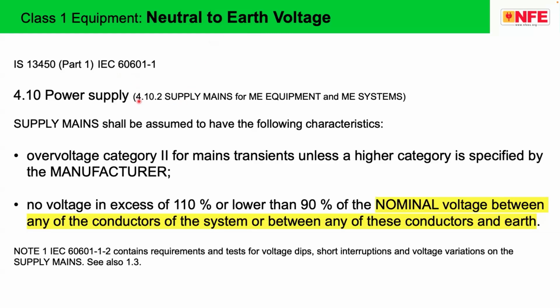I'm showing you from the standard. Every class 1 biomedical equipment is capable of working at 90% to 110% of the rated voltage continuously. You see here last, between any of these conductors and earth. Any of these live conductors, meaning line to earth, 230 plus 10% means 253 volt. Line to earth voltage 253, neutral to earth voltage 253 continuously. Still the equipment is capable of working, and this is a mandatory test in the equipment standard. 2 volt, 5 volt, 10 volt for a class 1 biomedical equipment is absolutely of no use.